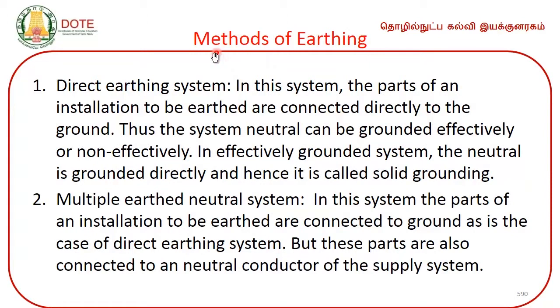Now, let us move on to the methods of earthing. One is the direct earthing system. In this system, the parts of an installation to be earthed are connected directly to the ground. Thus, the system neutral can be grounded effectively or non-effectively. In an effectively grounded system, the neutral is grounded directly and hence it is called solid grounding.